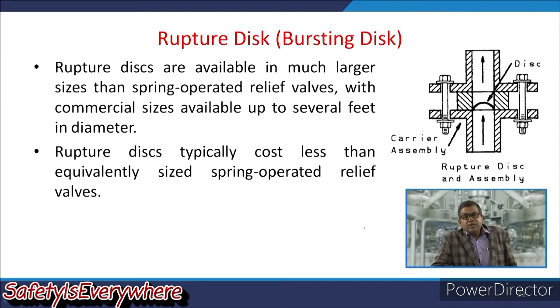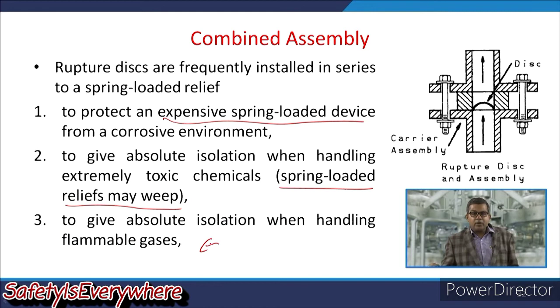Now there are certain combined assemblies. These rupture discs are frequently installed in series with the spring loaded relief valve to protect an expensive spring loaded device from a corrosive environment, because these spring loaded devices are very expensive. Also to give complete isolation when handling extremely toxic chemicals, because the spring loaded relief may weep when you are using those toxic chemicals. And to give absolute isolation when handling flammable gases, again this is very important.